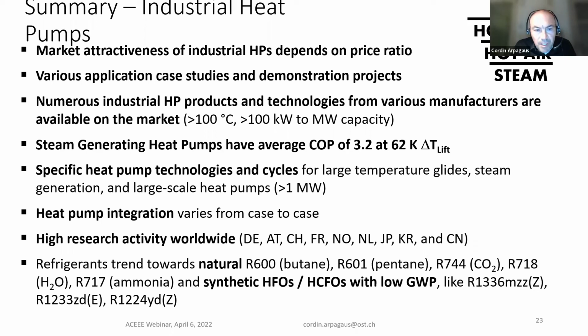Here you see a COP value of 3.2 at a 62 Kelvin temperature lift. That's an average value which can be assumed quite reasonable across many suppliers. The cycles can vary, and we've seen that large-scale heat pump technologies are available. Heat pump integration is typically case by case, depending on the situation, which means process engineers are needed to do this integration.